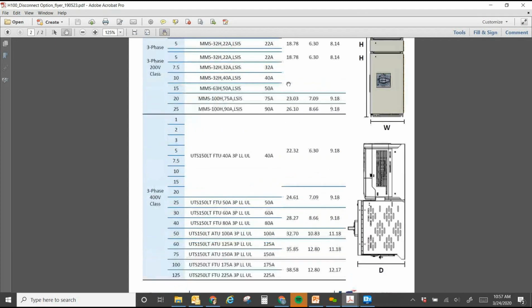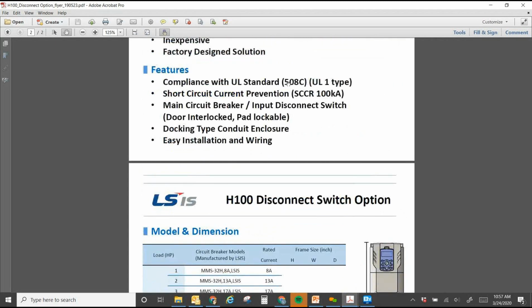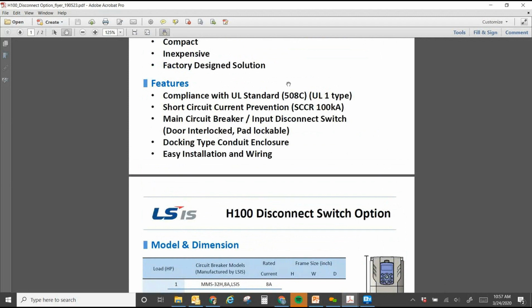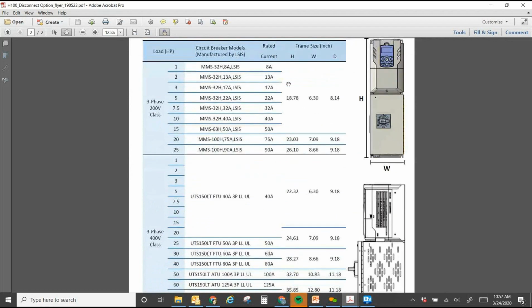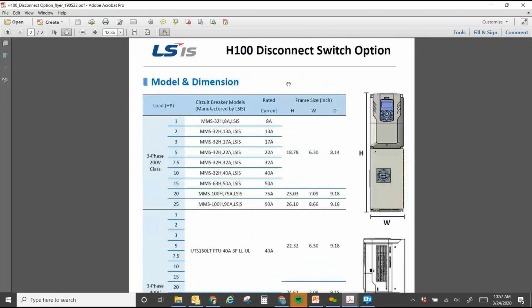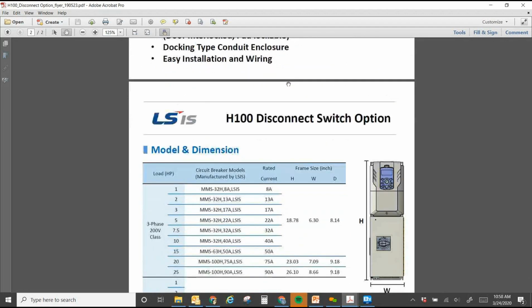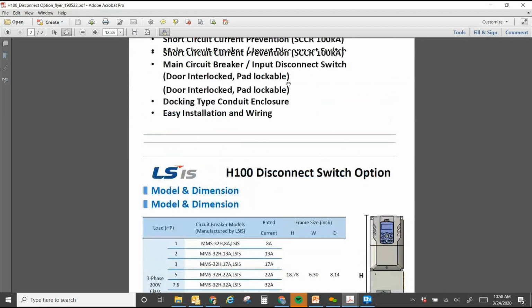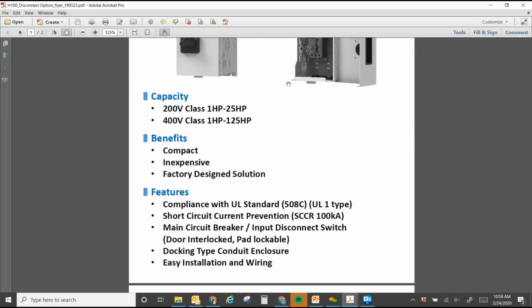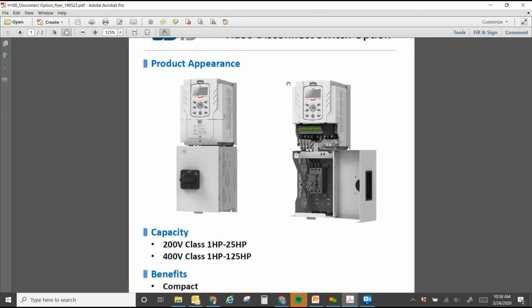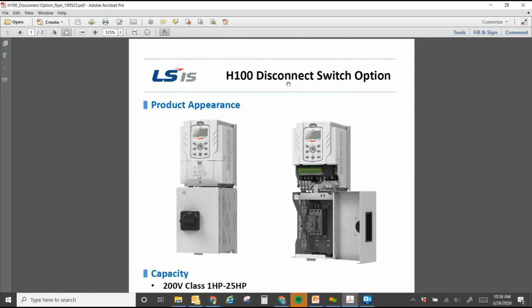Here's the dimensions, here's kind of how it looks. Easy to wire, easy to install, you could use a conduit on it. The main benefit of this is it's just a disconnect that gets mounted onto the bottom of the H100. So someone asked what's the difference between a bypass? The main answer is this is not a bypass, it's just a disconnect. There's no bypass functionality in here, no contactors or anything like that.